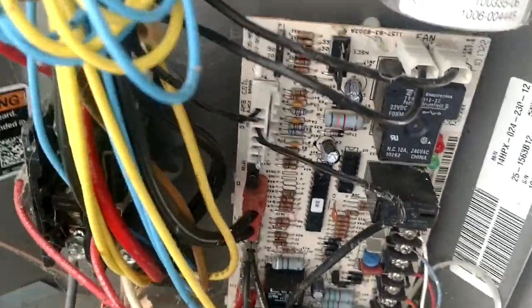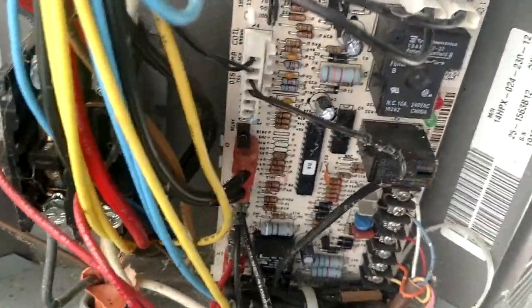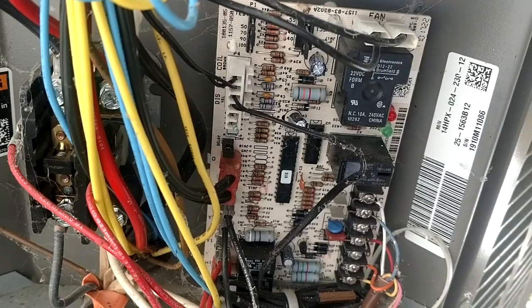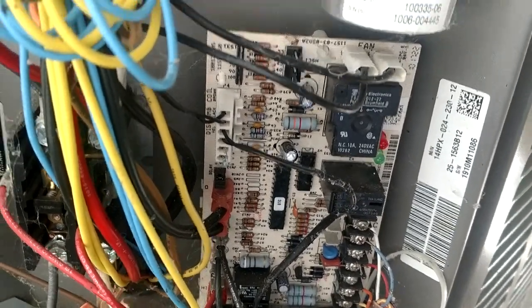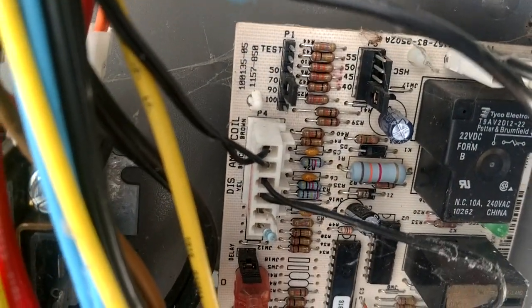And inevitably, you will get some service calls on these this year. More than likely it will be newer units that were just installed back this past summer, and the install guys did not move that pin down, and it is not going to thaw out properly. The fix for it is tremendously easy — you just reach in here and literally move the pin down one notch.